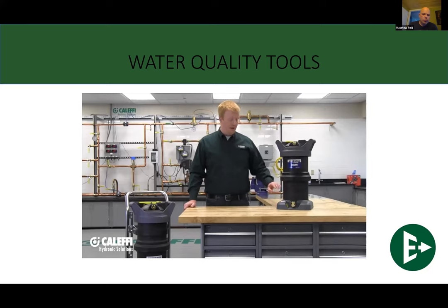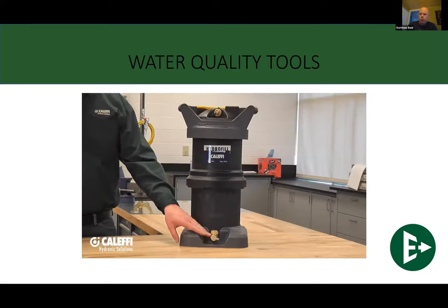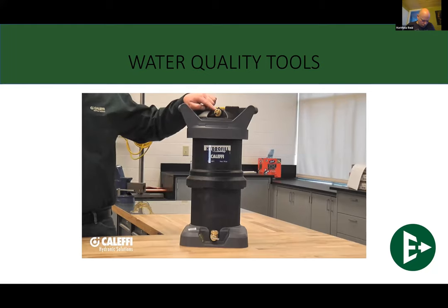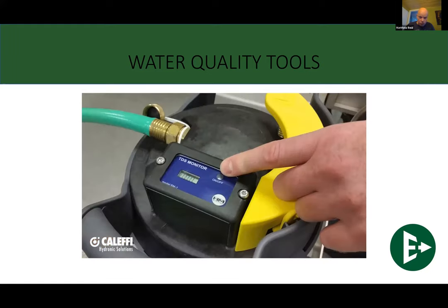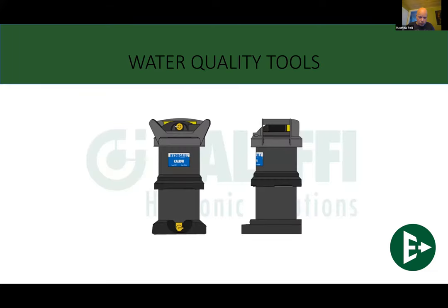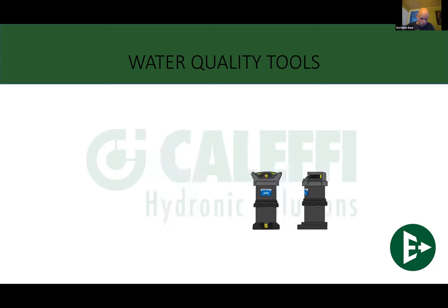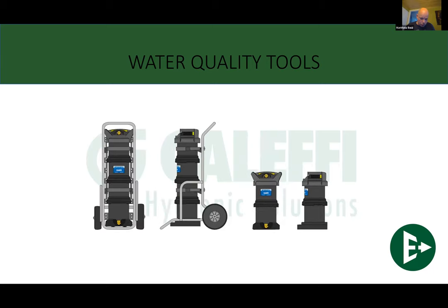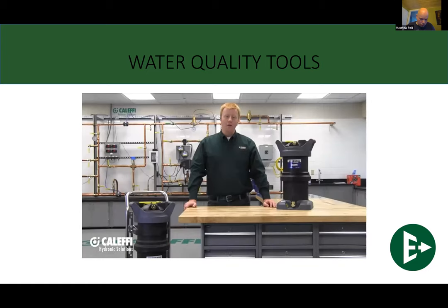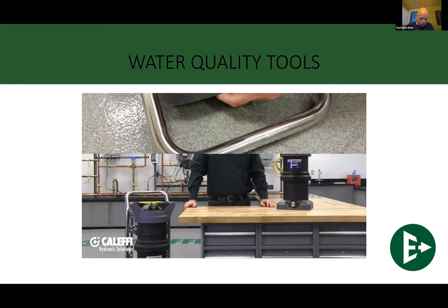The two-bag model that we have here is going to have an on-off valve at the very bottom with a 3/4 inch garden hose thread connection. We're going to have a 3/4 inch garden hose thread connection on top as well with a cap. You're going to have a TDS meter on top, which is going to measure your total dissolved solids in parts per million. You'll notice here that the two-bag model is going to be fairly portable and pretty small, while our four-bag model is going to have a nice stainless steel cart to help you get it around. Depending on your site water, you'll be able to get about 1,000 or more gallons of treated water out of your two-bag model and roughly about double that out of our four-bag model.